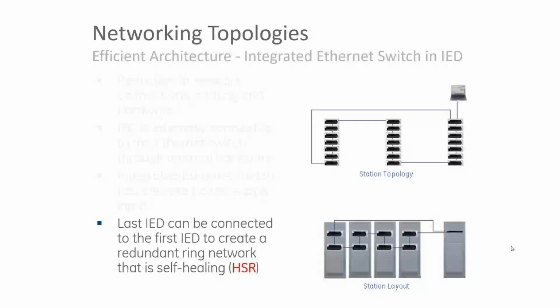And then one of the standards that we use for that is HSR, High-availability Seamless Redundancy Protocol, which is a protocol to create devices in a ring and be able to self-heal that ring, switch that ring seamlessly without any recovery time. However, the devices have to be able to support that standard protocol. So if the devices support that standard protocol, we can do this, and it becomes a seamless ring, and any break or recovery time is inconsequential.